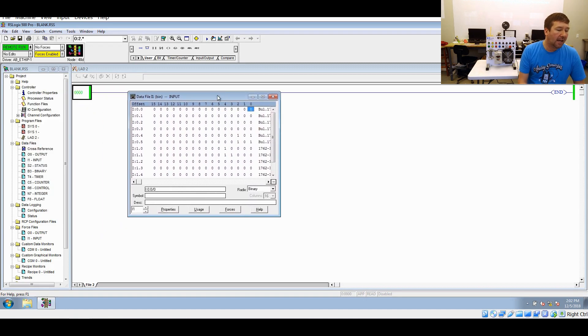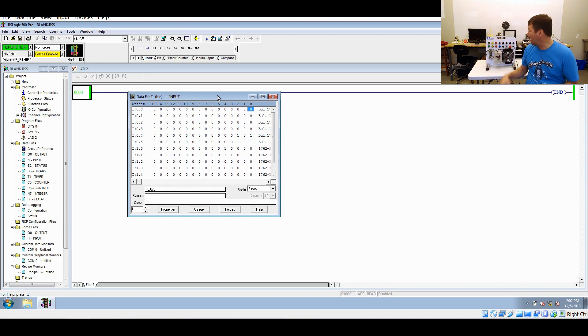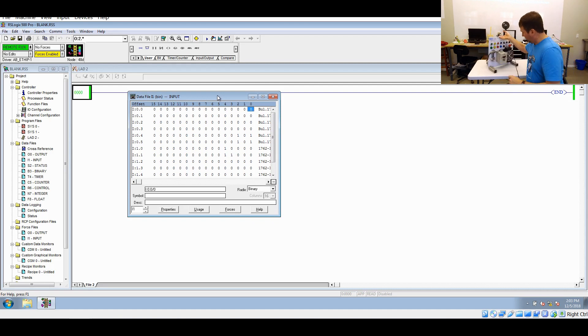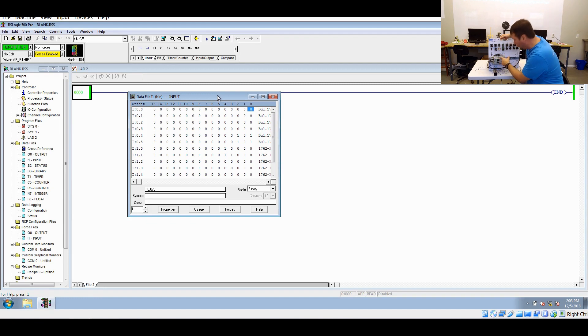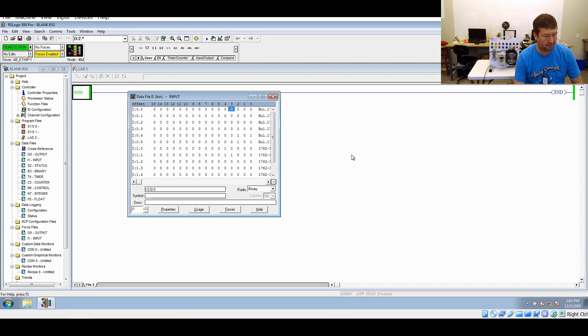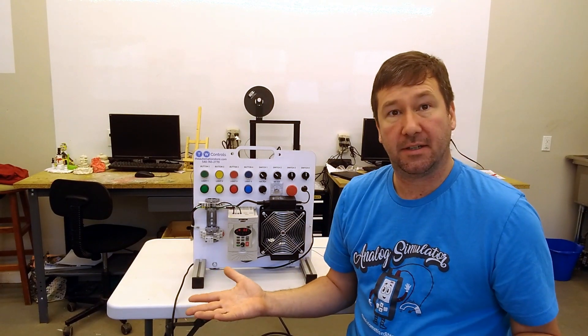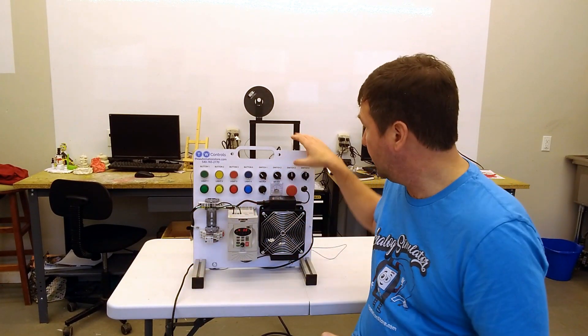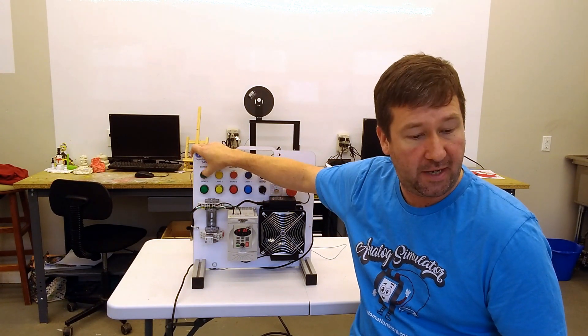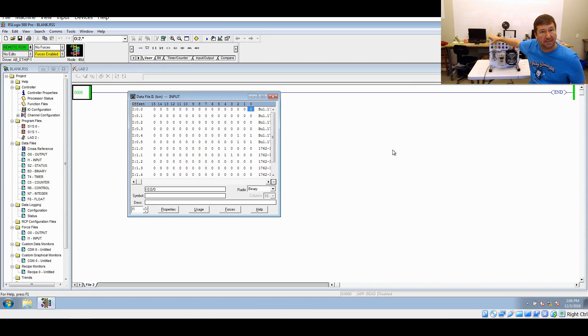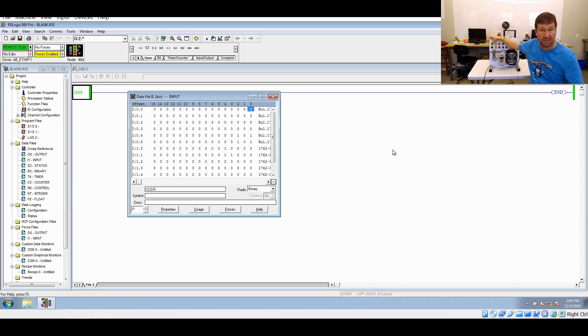Double-click it and we see our inputs. When you open it up you'll see there's a bunch of zeros there — there may actually be some ones, depending on exactly how you have yours wired. We have ours wired per our previous Wiring It Up To Get Started video. The top row are the inputs that you actually see on the top, and you have I/0 through I/9. So what happens if we push a button? We have a blank program running. You see we're going to push our green button, which is wired to input zero. Over here you can see it goes to one — I release it, it goes back to zero. So this button, which is wired to input zero on the PLC, is changing the state of the zero in here.